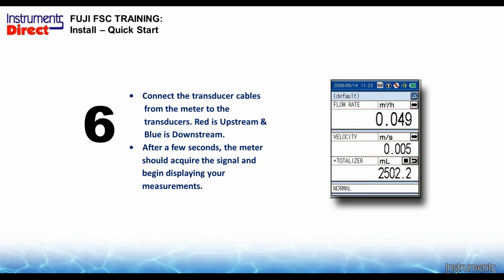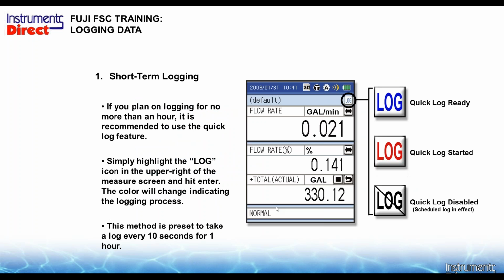Again, this meter is programmed in metric, but you can flip the switch to program it in English. And the way we send them out the door, this GUI interface, the top line would read flow rate, the next line would read velocity, and the next line would read totalization. And this would be the conditions. You can see it's in the normal mode there. Some neat features of this device is that it has the slickest data logger in town.